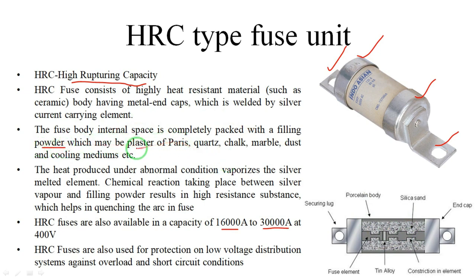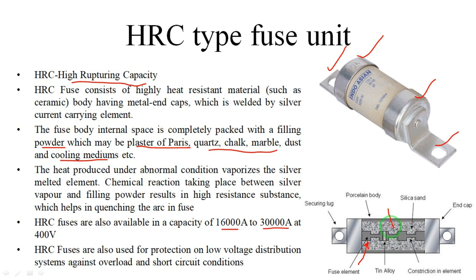The filling powder material may be plaster of paris, quartz, chalk, marble dust, or other cooling mediums. The heat produced under abnormal operating conditions vaporizes the silver fuse element. A chemical reaction occurs between the silver fuse element and the filling powder, resulting in high resistance which helps to quench the arc in the fuse. This causes it to melt and open the circuit.